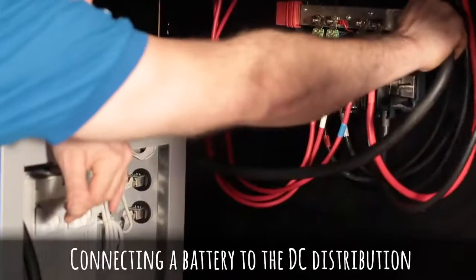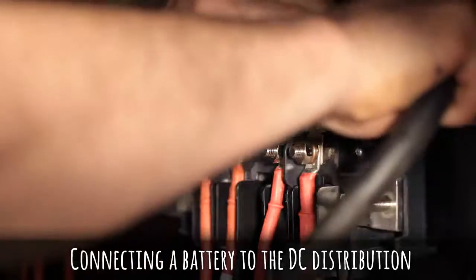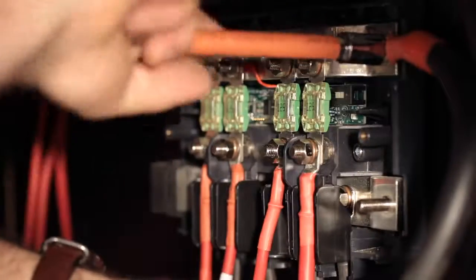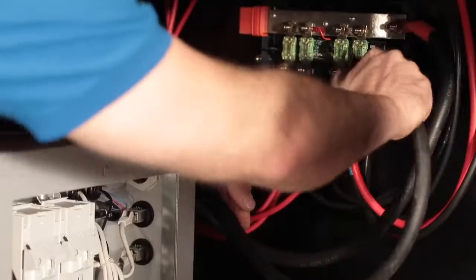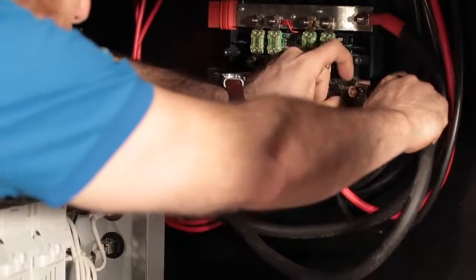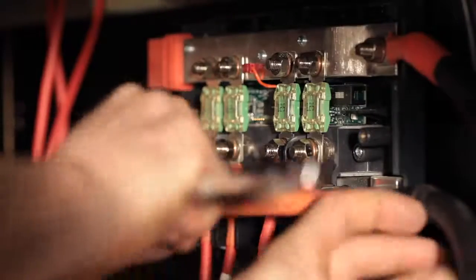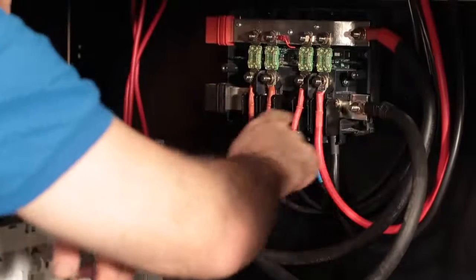Once these cables are securely in place, you can then attach the battery cables to the DC distribution bus bars. There are larger connection points on each end. Be very conscious at this point to observe polarity. In this case, this is using a lithium battery, and the lithium battery is not yet switched on, so there's no voltage at these terminals.